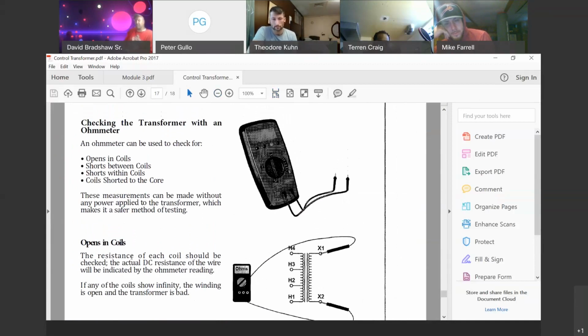So here what they're trying to show you is they're looking to see if there's an opening in the coil, an opening in the secondary. If there was an opening, what you'd see on the meter is infinity. If this was a working transformer on the secondary, you'd probably see around 6 ohms. Your lab will tell you what type of resistance to expect.